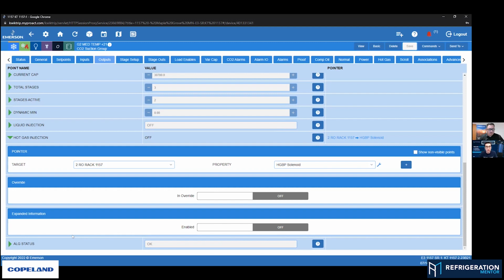You would have to now go from here and make sure the wiring goes to that exact solenoid, and you've got to see on there, is this the hot gas bypass solenoid? I think that's what they put, HGBP, but that hot gas injection solenoid. This is your verification. Yes, the OEM may have set this up and programmed this for you, but sometimes mistakes happen. Maybe they loaded up a program that wasn't fully configured. So as a startup technician, you've got to go and double check this. And I love that you showed that, so thank you, because these are the things that we don't see on a synthetic rack really.